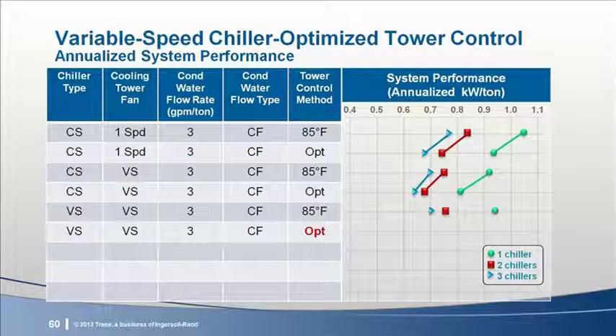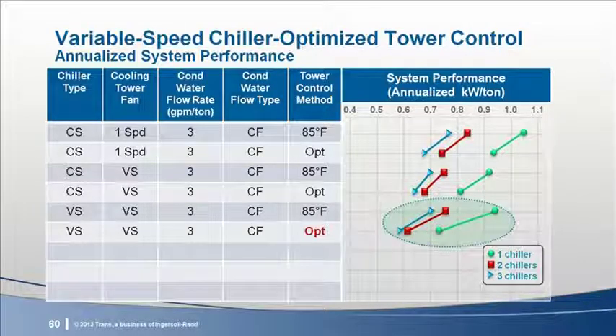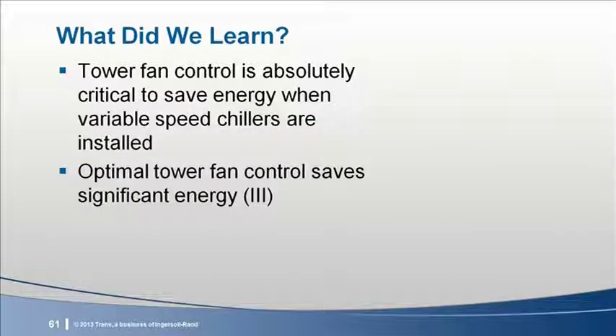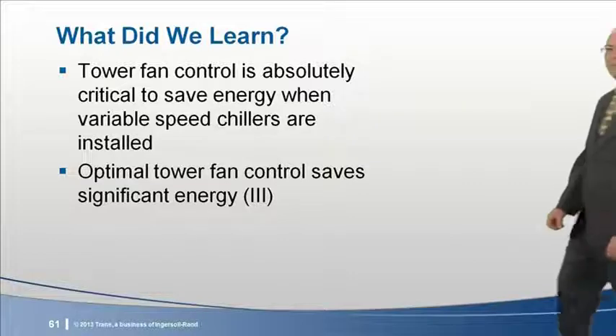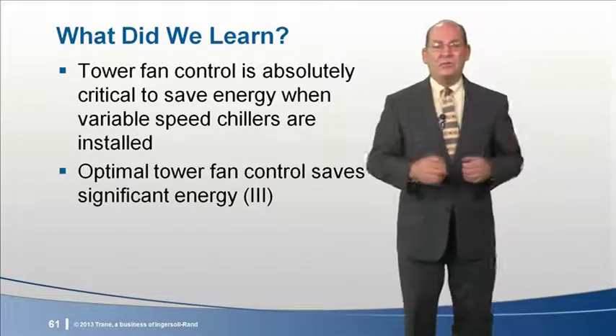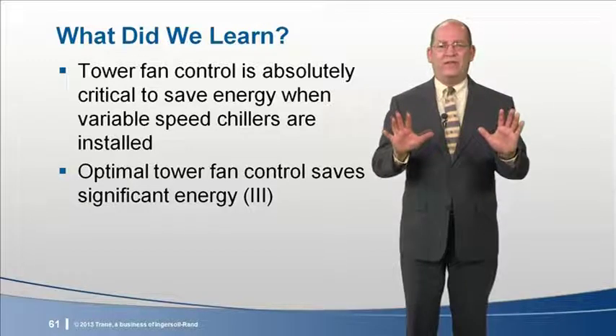So, let's do that by applying optimal cooling tower fan control. Note the huge change from improper tower fan control in all cases. So from an energy perspective, optimal tower control has a significant reduction, in line with that of VFDs on cooling tower fans. Our conclusions are that the tower fan control is critical when variable speed chillers are installed, and once again, optimal tower fan control saves significant energy.